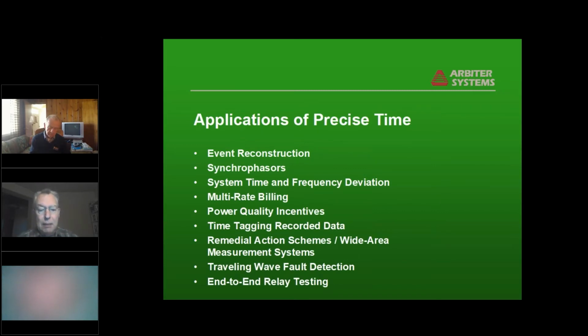So here are some of the applications that we see time being used for. Event reconstruction in the event of a fault. Time tagged records are very, very helpful. Matter of fact, essential in figuring out the sequence of events and what happened. Synchrophasors, people are getting to be quite familiar with these. Basically very precise power measurement that allows us to monitor the system from a wide area perspective. Measuring system time and frequency deviation.